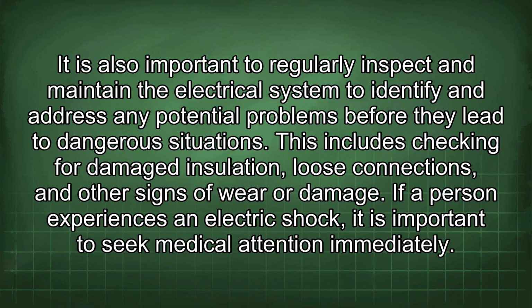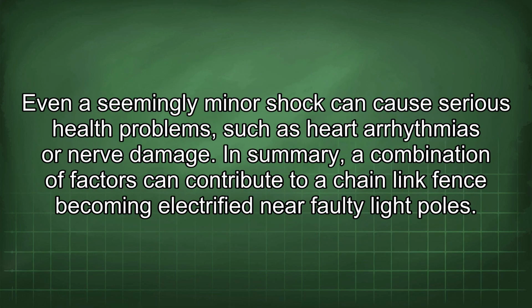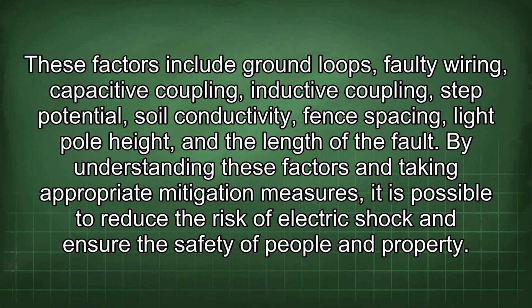If a person experiences an electric shock, it is important to seek medical attention immediately. Even a seemingly minor shock can cause serious health problems, such as heart arrhythmias or nerve damage. In summary, a combination of factors can contribute to a chain-link fence becoming electrified near faulty light poles. These factors include ground loops, faulty wiring, capacitive coupling, inductive coupling, step potential, soil conductivity, fence spacing, light pole height, and the length of the fault. By understanding these factors and taking appropriate mitigation measures, it is possible to reduce the risk of electric shock and ensure the safety of people and property.